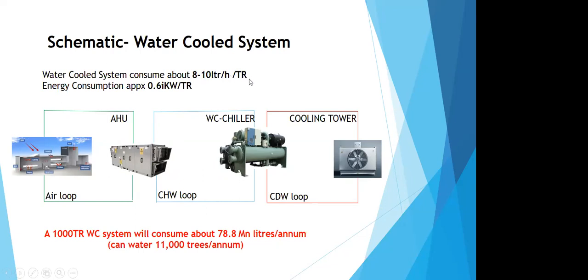We all know that the cooling tower consumes roughly 1.2% of the circulating water flow rate. If we convert that into liters, the thumb rule would be 8 to 10 liters per hour per ton of refrigeration. So that is pretty high. The energy consumption for this chiller would be close to 0.6 kW per ton, or maybe slightly lower as well, because we have more efficient chillers available in the market.